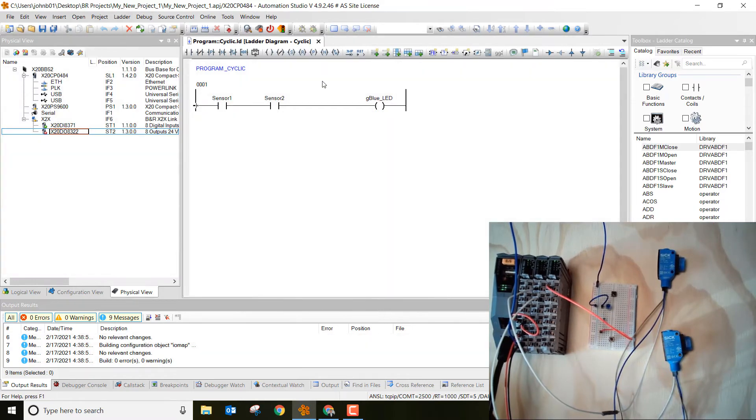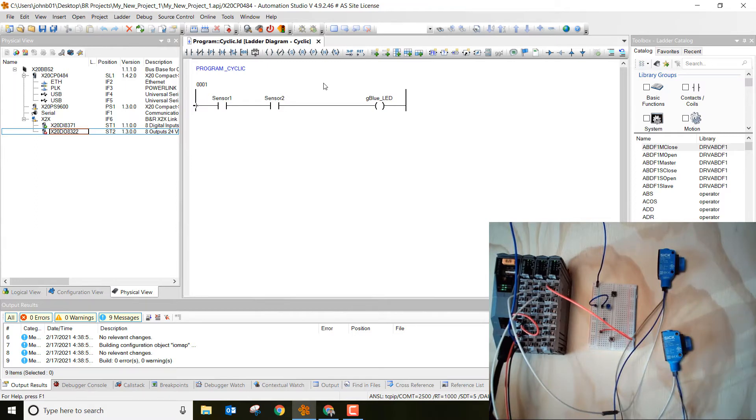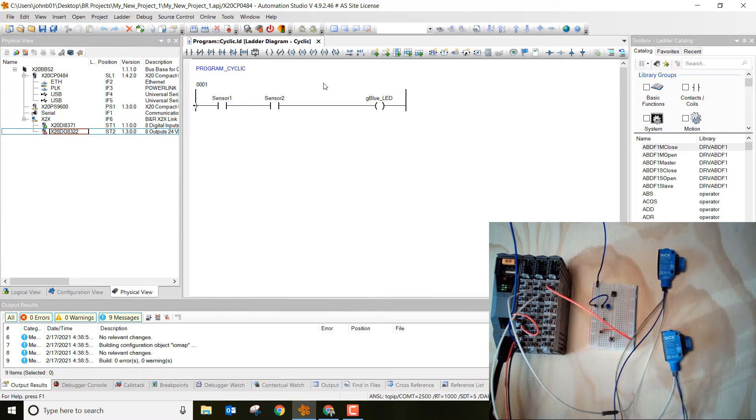The other way, which I've talked about in other videos, is if we don't have Automation Studio but we still want to troubleshoot and see what's going on with this controller, we can open up a browser as long as we're hooked up with an Ethernet cable from the controller to our PC. We can open up a browser and type in the IP address of this controller and then look at the system's diagnostic management tool.